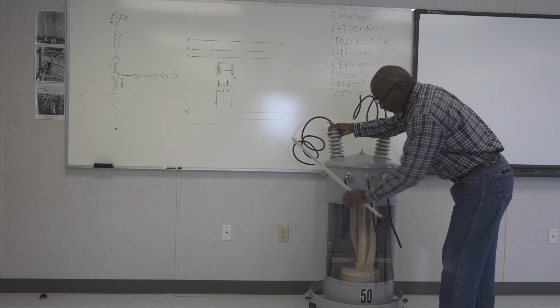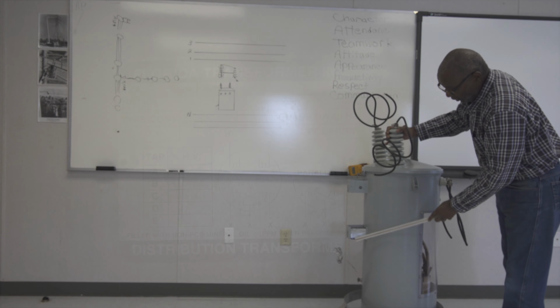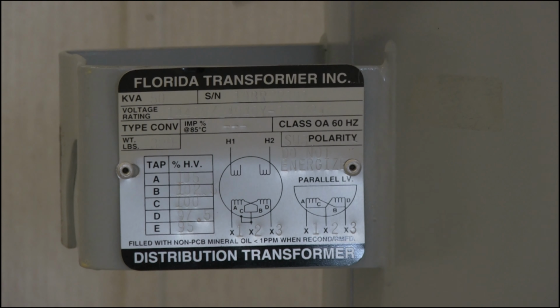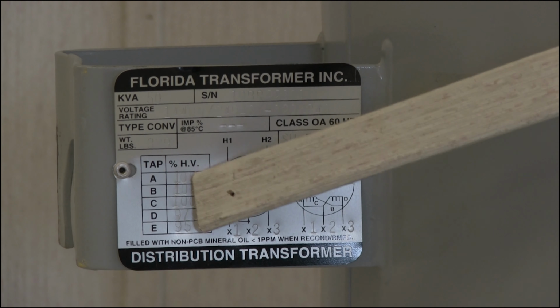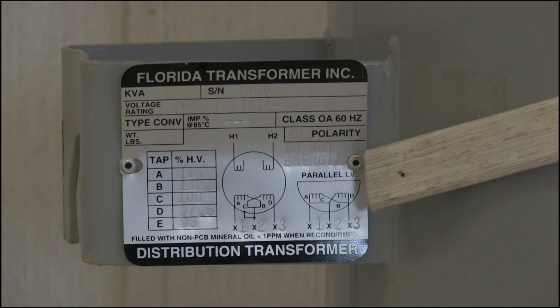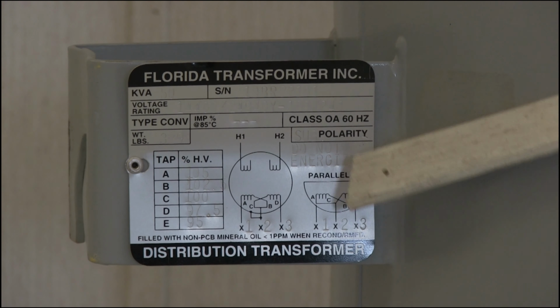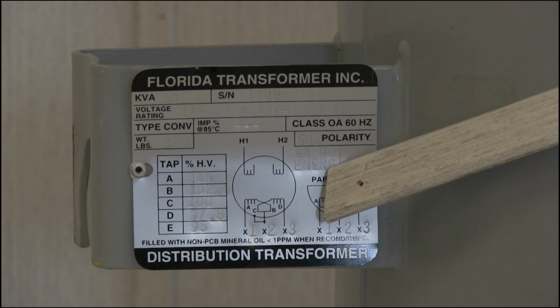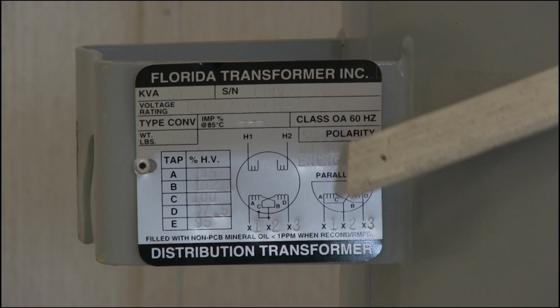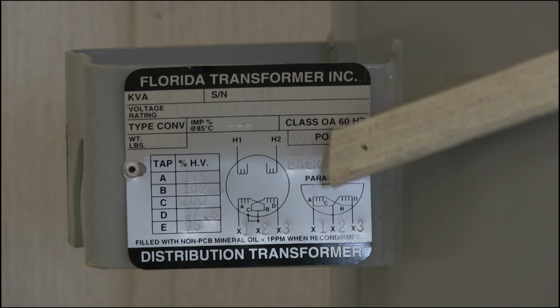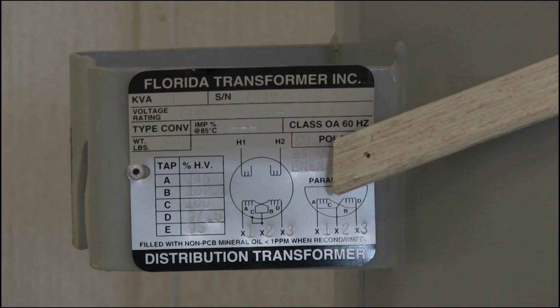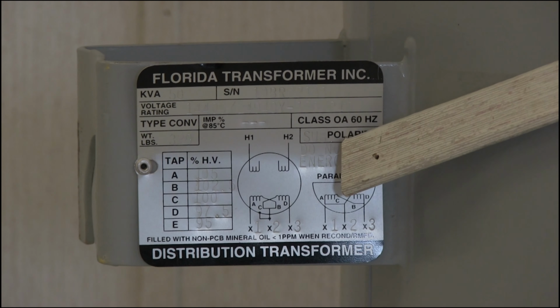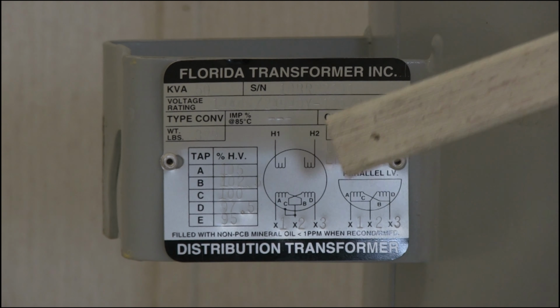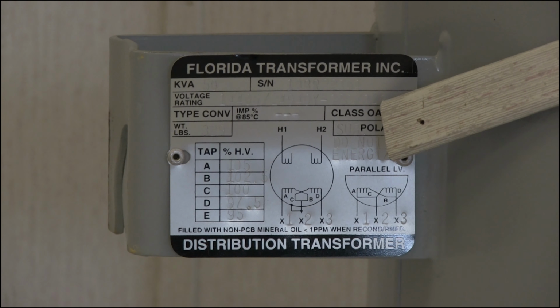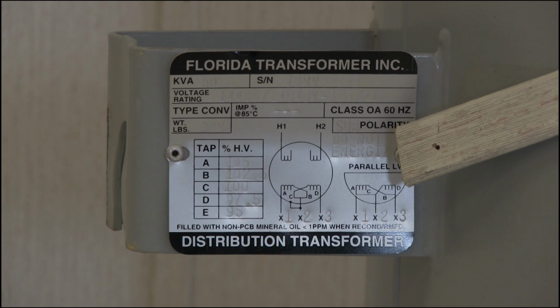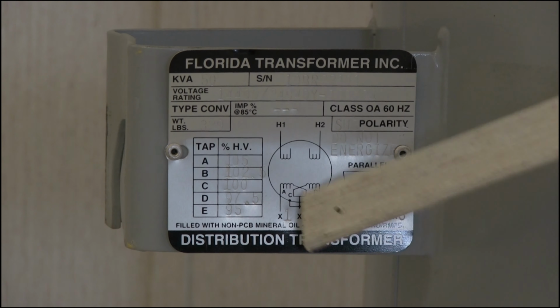Also on this, another important piece that you want to look for on your transformer is this is considered a data tag. The information that you will find on your data tag is, of course, the kVA size, the polarity, the weight, also the gallons of oil, of course, a serial number and a manufacturer's name, and the polarity of the transformer.